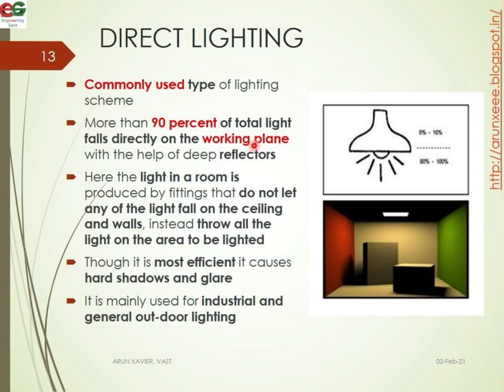In direct lighting, deep reflectors are used. The light fittings do not let any light fall on the ceiling and walls. All of the light is thrown directly onto the area to be illuminated. It is the most efficient type, but it causes hard shadows and glare.